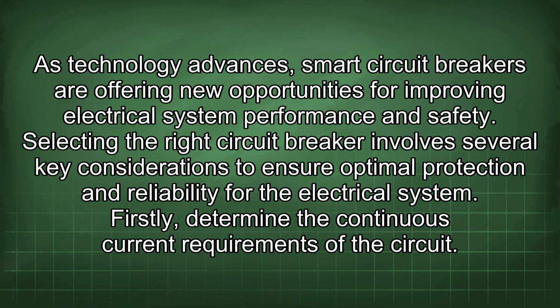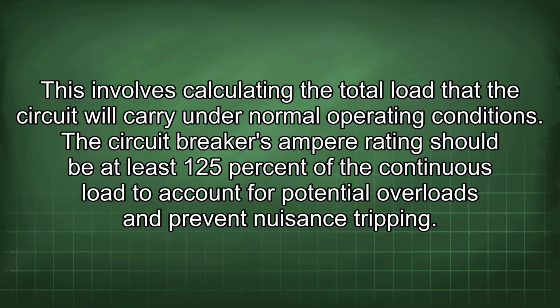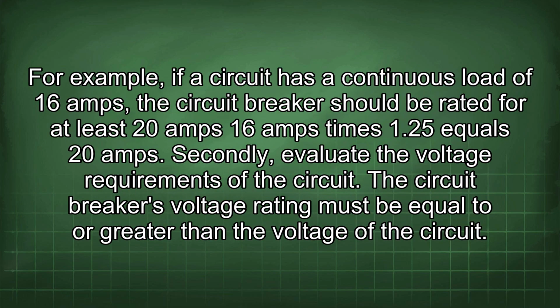Selecting the right circuit breaker involves several key considerations to ensure optimal protection and reliability for the electrical system. Firstly, determine the continuous current requirements of the circuit. This involves calculating the total load that the circuit will carry under normal operating conditions. The circuit breaker's ampere rating should be at least 125% of the continuous load to account for potential overloads and prevent nuisance tripping. For example, if a circuit has a continuous load of 16 amps, the circuit breaker should be rated for at least 20 amps. 16 amps times 1.25 equals 20 amps.